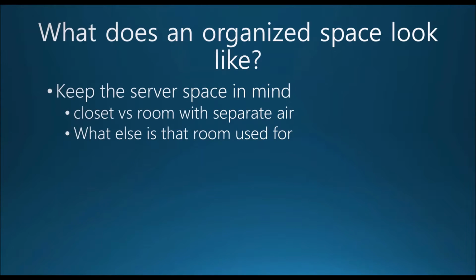But if that room isn't being used at all, then again not only the dust, but you have all that hot air just staying in there. So try to find out exactly what else that room is used for. If it's being used for areas where there's spray glue or anything like that, that'll get attached to the dust and get sucked into that server. Try to keep that in mind when designing that space, keep it separate from everything else, and think about the cooling and the amount of dust that's going to be in that room.